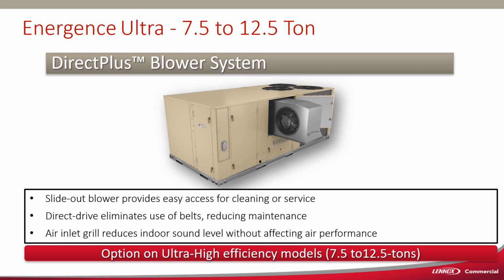The 7.5 through 12.5 ton, or the B box, has a belt drive motor, but we also have an option called the Direct Plus. And this is a forward curve fan foil fan, or airfoil fan, excuse me. And it is direct drive DC motor on it, and it is a truly variable motor. If you see this motor housing that's in there, you see it being slid out, it's on drawer slides. This is a complete component. You can pull this out and order the whole component with one part number.